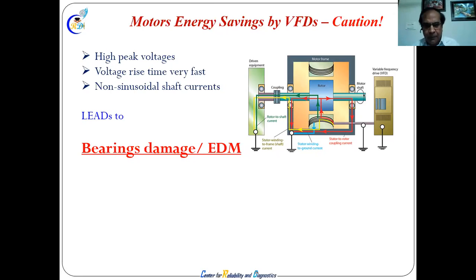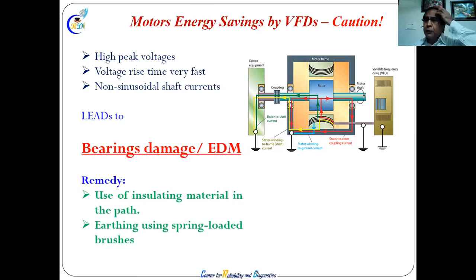They must earth properly, and bearing damage, electro discharge machining, should not be there within the bearing. So the bearing, which is supposed to run properly in a concentric way, is now running a machining. Electric discharge machining is going on inside the bearing. Very tough problem, very serious problem. So you have to do it by insulating the bearing or earthing.